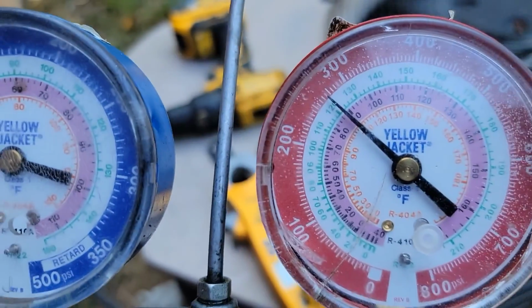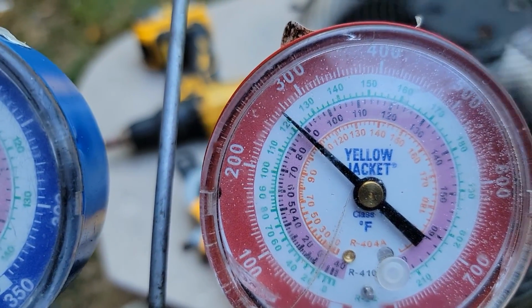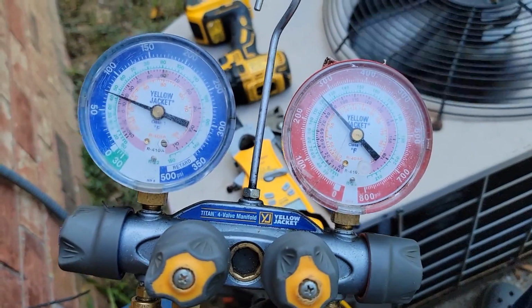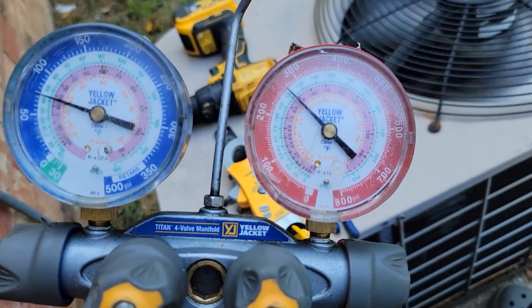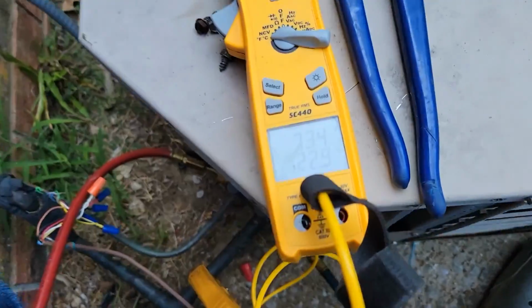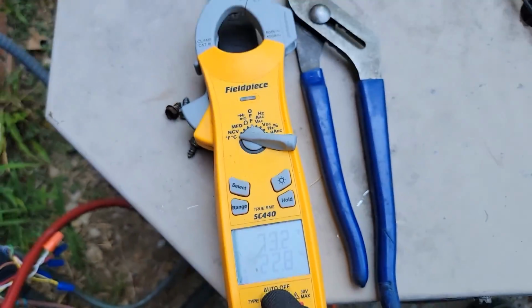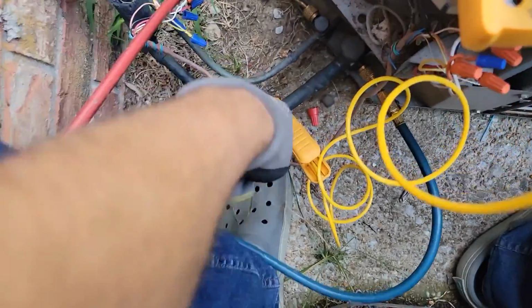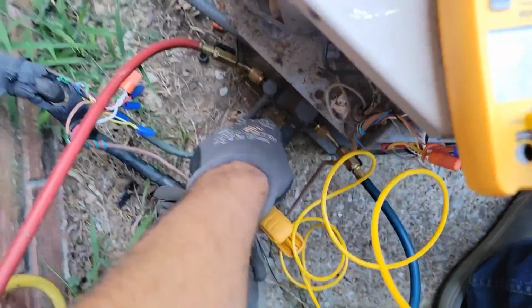Suction pressure is 75, head pressure is about 265, 270. So suction pressure looks pretty good. Head pressure, it looks pretty good. A little bit high, maybe. Vapor line temperature 73. Yeah, that's definitely got to come down, but it's getting cold.